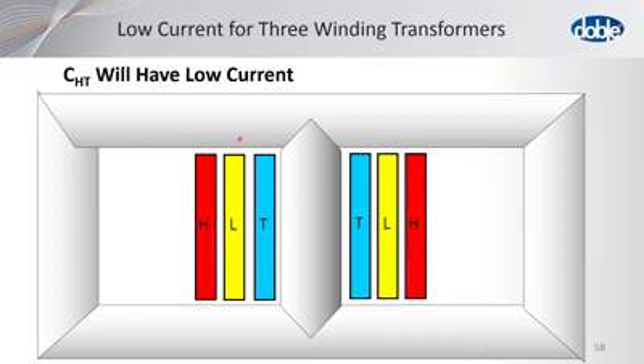You are only getting the skirting effects around the low voltage winding. Of course, it'll happen on the bottom also. So you're getting very, very low values. Notice that in this case, this is a case right here where that's the situation. And notice it's less than 1 milliamp. That's the way we identify that there may be a shielding problem or a shielding situation. I don't want to indicate that this is a problem. It's just the situation. So that's why this is very low. Notice by comparison, it's 41 and 21 milliamps for the other insulation system. Now this one was given a bad rating because it didn't match up nicely, but we informed the client that this was okay because of the low currents.